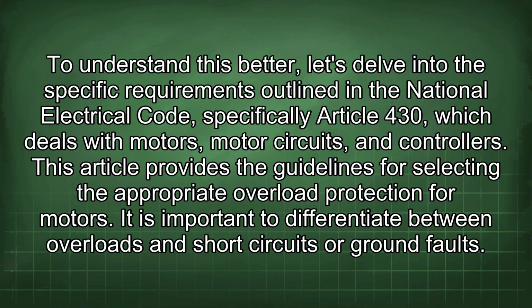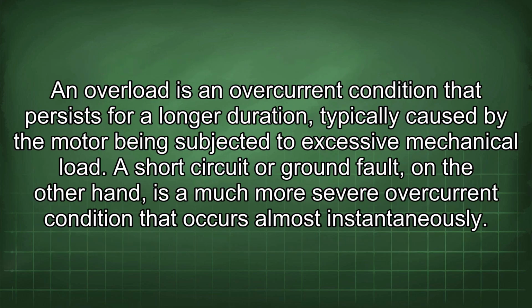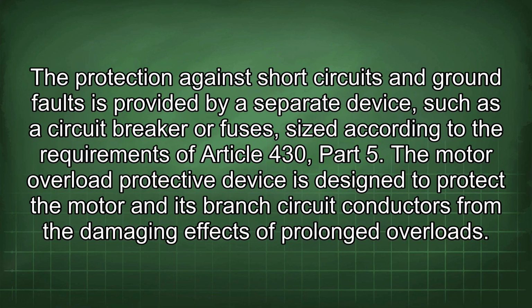It is important to differentiate between overloads and short circuits or ground faults. An overload is an overcurrent condition that persists for a longer duration, typically caused by the motor being subjected to excessive mechanical load. A short circuit or ground fault, on the other hand, is a much more severe overcurrent condition that occurs almost instantaneously. The protection against short circuits and ground faults is provided by a separate device, such as a circuit breaker or fuses, sized according to the requirements of Article 430, Part 5.